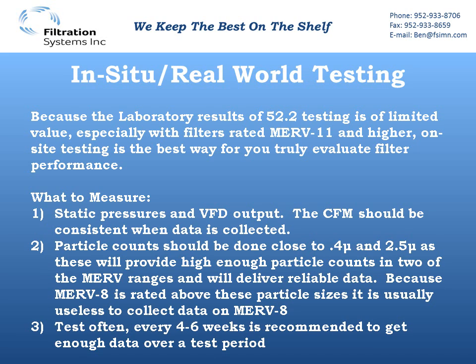The third thing to do when doing an in-situ test is to test often — every four to six weeks, and maybe more if you have the ability, but every four to six weeks seems to be a minimum. That way you'll have enough data; the more data you have, the more reliable it becomes, and you don't see big swings or outliers in the information.